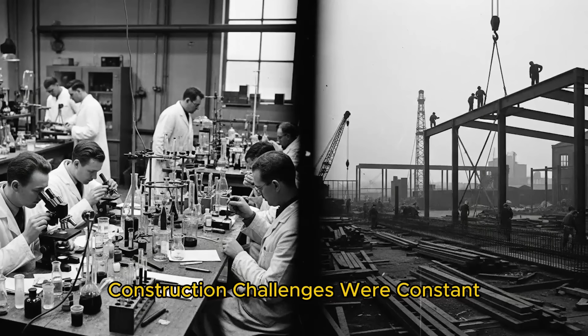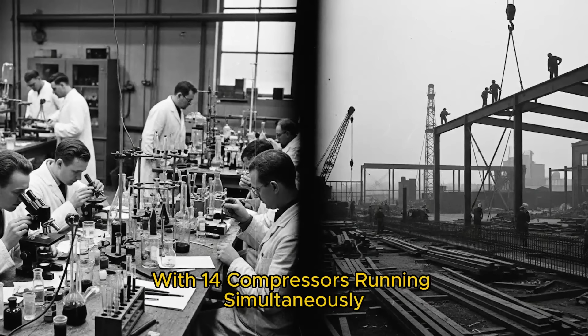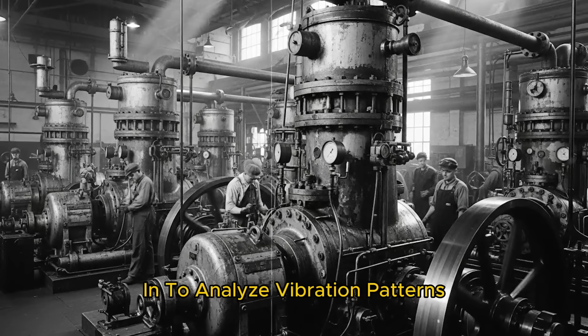Construction challenges were constant. One unexpected problem was vibration. With 14 compressors running simultaneously, the building complex would vibrate at specific frequencies. Engineers discovered that at certain operating conditions, these vibrations would resonate with building structures, potentially causing equipment damage. Solutions required installing thousands of vibration dampening systems and redesigning some building foundations. Acoustical engineers were brought in to analyze vibration patterns and develop solutions, expertise borrowed from the aerospace industry.